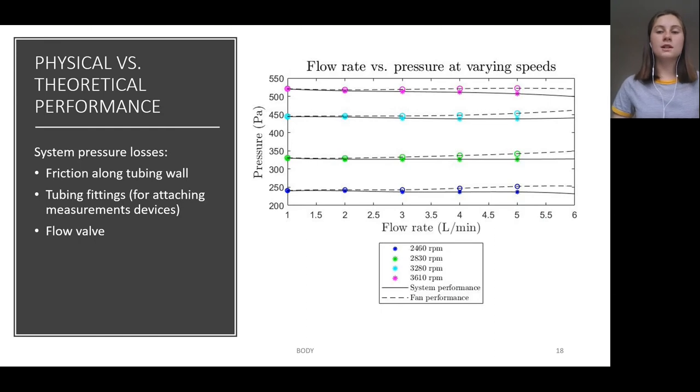The performance curve generated for the physical fan is shown here. The solid lines depict the system's performance, including tubing and fittings, whereas the dashed lines are estimations for the fan's performance on its own. The key takeaway is that over the range of varying flow rates, the pressure rise remains relatively constant, which is important for achieving a continuous pressure as in a CPAP machine. Unfortunately, the fan's behaviour for higher flow rates could not be measured due to limitations in the flow meters available — the rotameter used could only measure between 0.4 and 5 litres per minute.